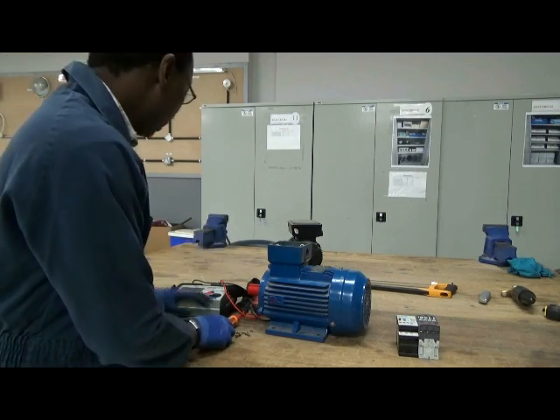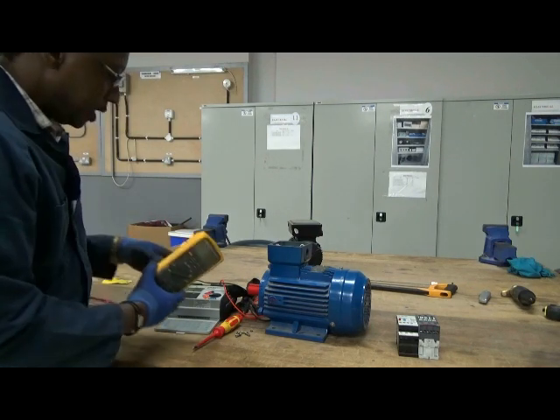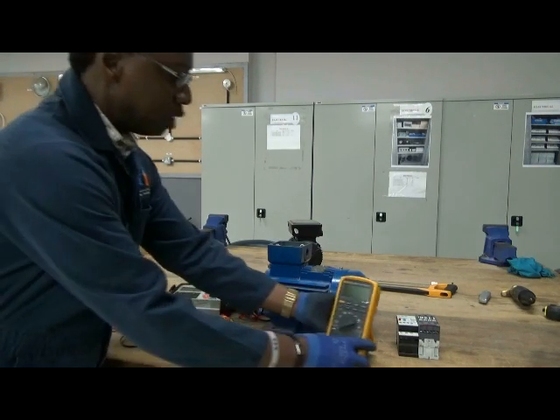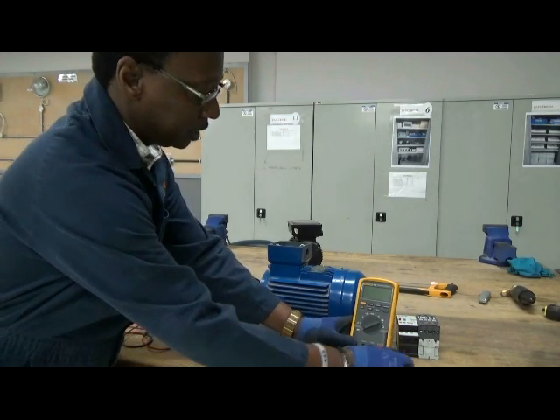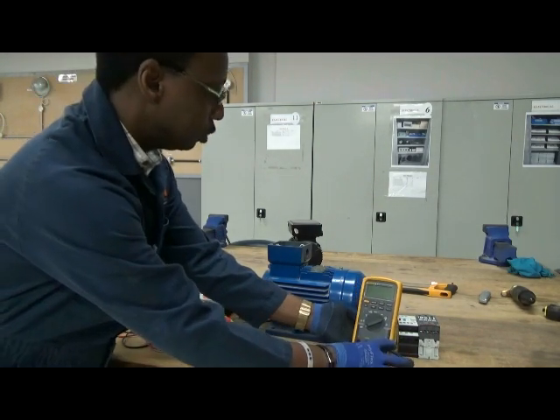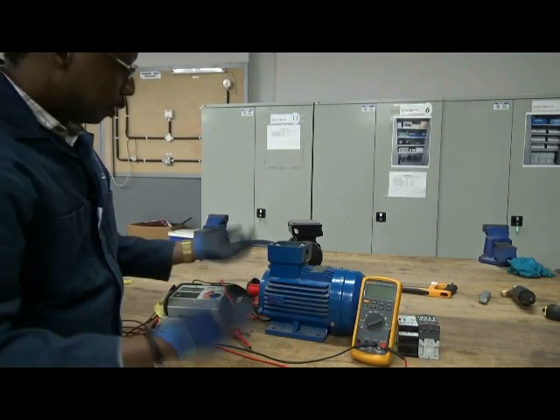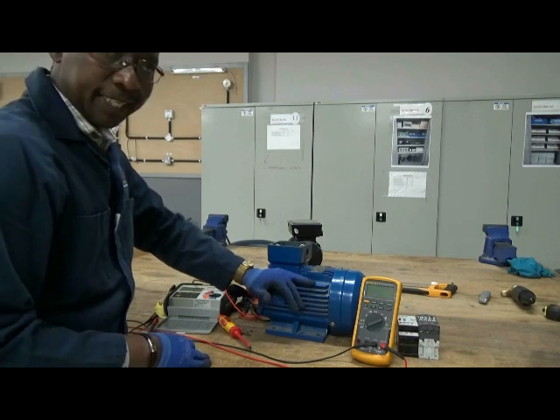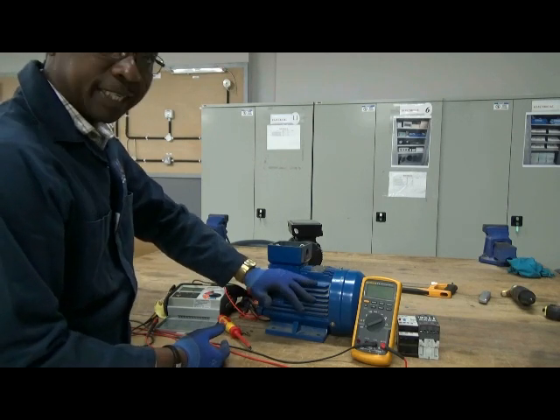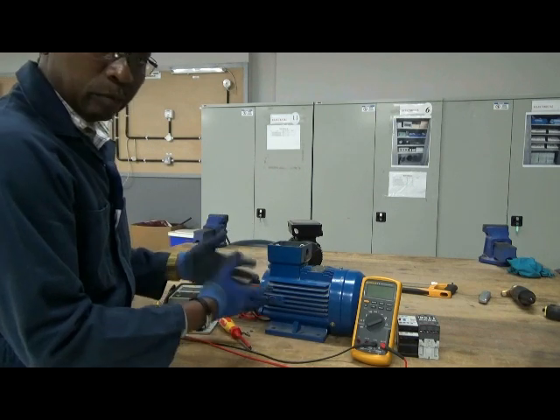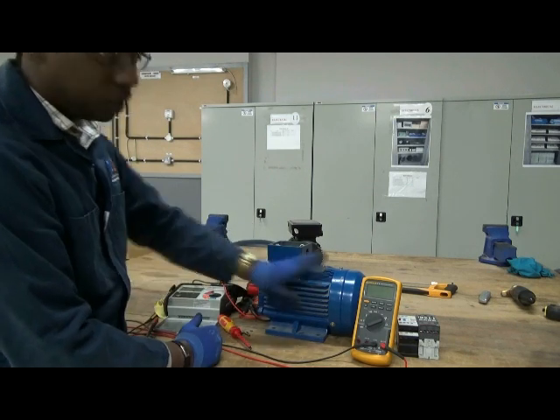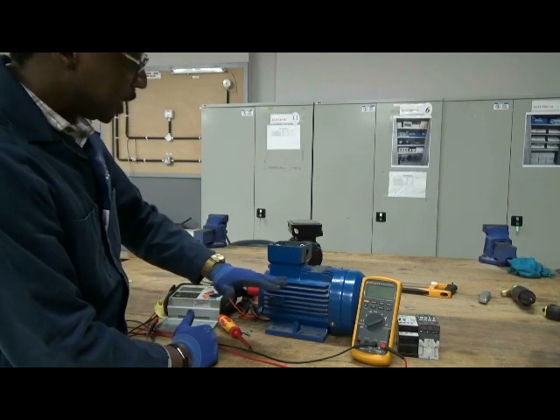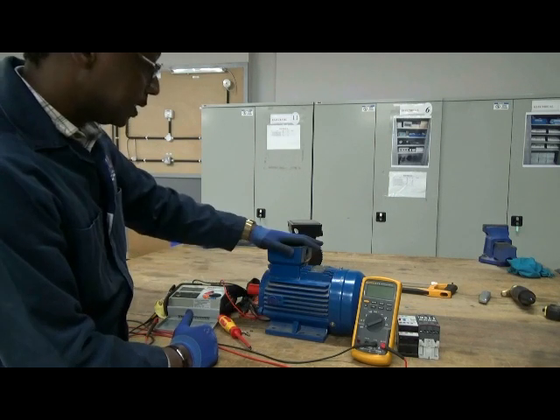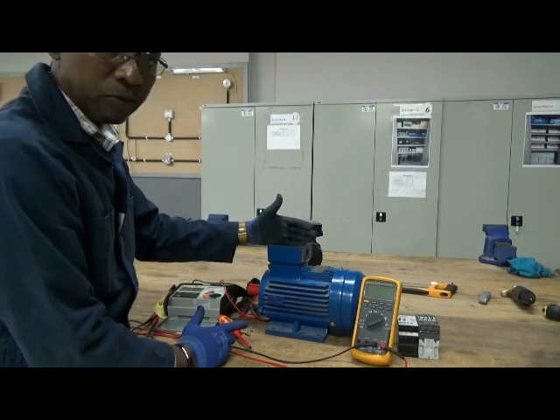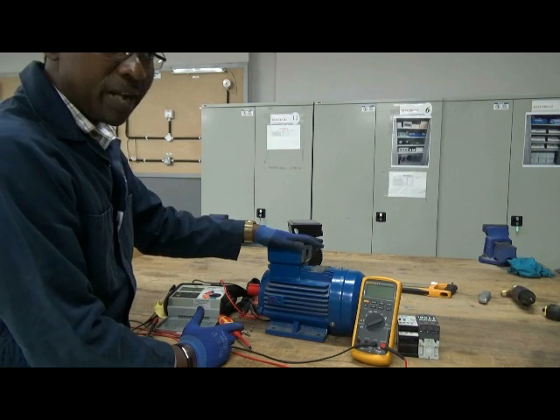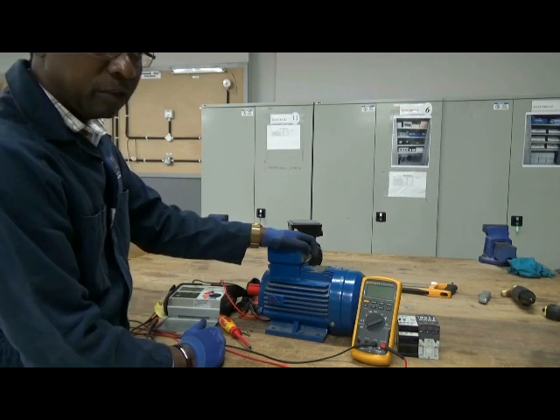Right, so what I'm going to do now is to use one of these machines. I'll start off with a multimeter, which is a measuring instrument that we use to measure the resistance of windings. It is possible that the windings can be open-circuited, and once they are open-circuited, then we don't get a magnetic field in the stator, and the motor will not be running. So we need to check and see if the windings are continuous. All of them, there are just three of them. So we must test each and every winding, first and foremost, to see if they're not open-circuited.